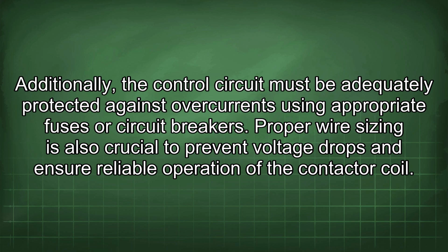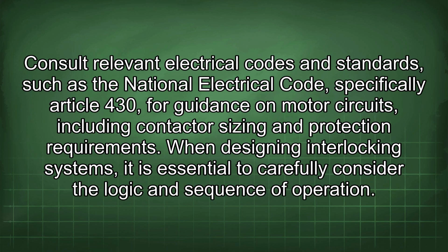Proper wire sizing is also crucial to prevent voltage drops and ensure reliable operation of the contactor coil. Consult relevant electrical codes and standards such as the National Electrical Code, specifically Article 430, for guidance on motor circuits, including contactor sizing and protection requirements.